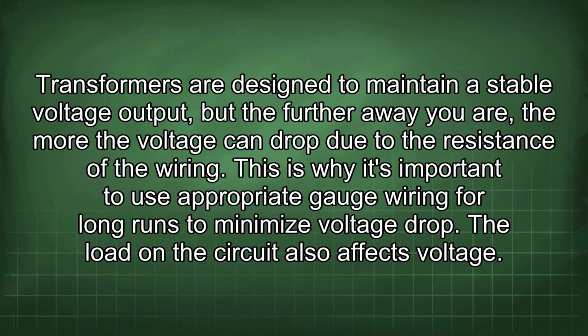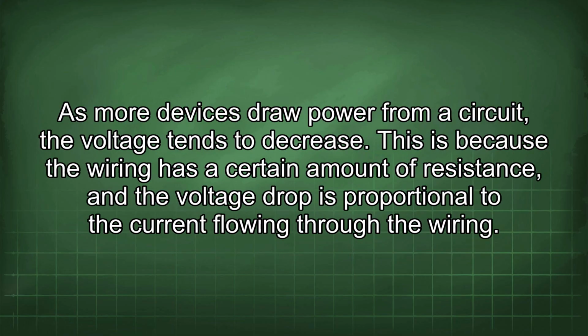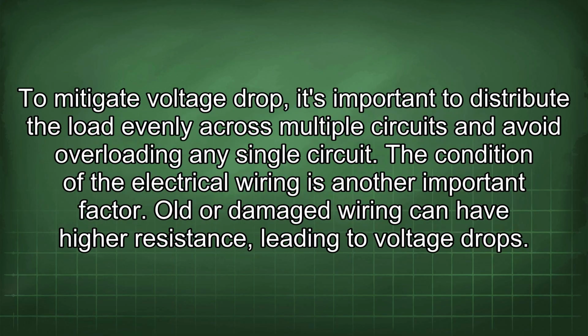The load on the circuit also affects voltage. As more devices draw power from a circuit, the voltage tends to decrease. This is because the wiring has a certain amount of resistance, and the voltage drop is proportional to the current flowing through the wiring. To mitigate voltage drop, it's important to distribute the load evenly across multiple circuits and avoid overloading any single circuit. The condition of the electrical wiring is another important factor.